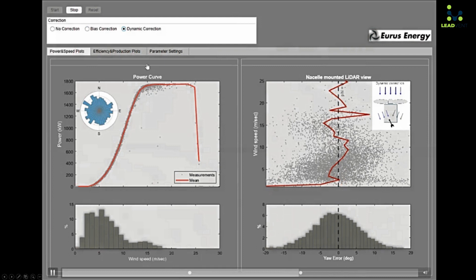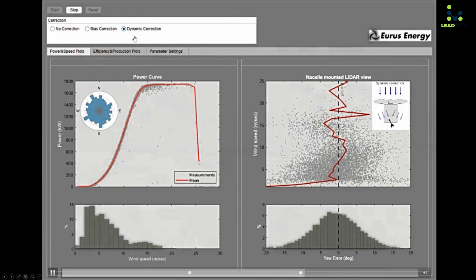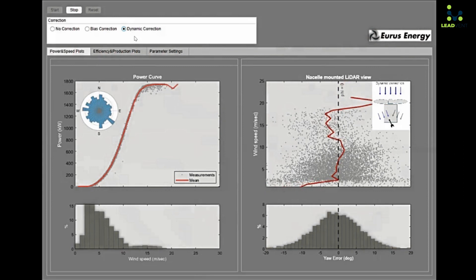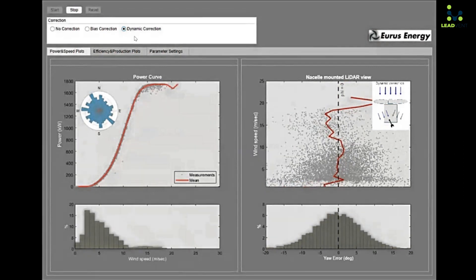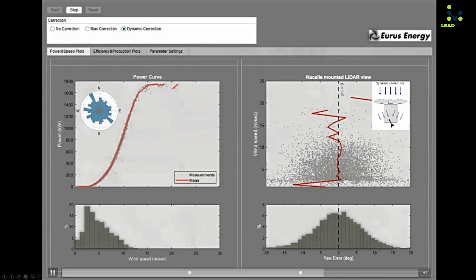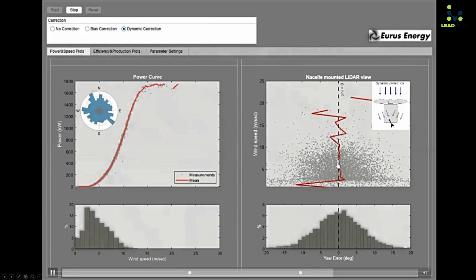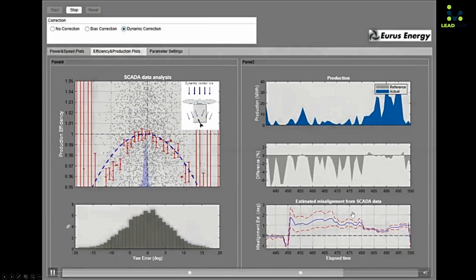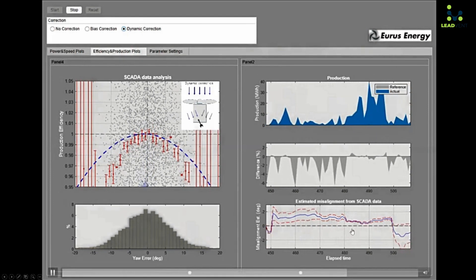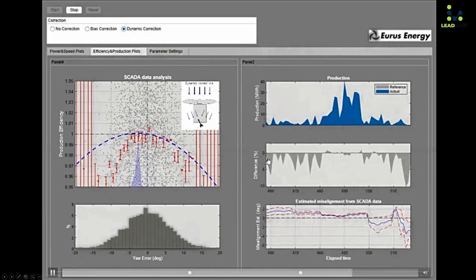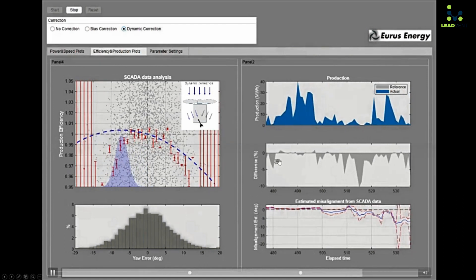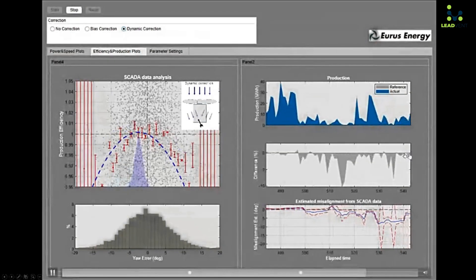Once we activate the dynamic correction, which corrects the misalignment depending on wind speed, ambient temperature, and yaw direction, the production difference, which was about a few percent, almost becomes zero.